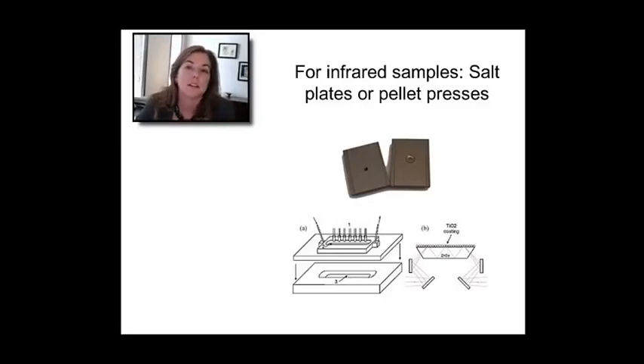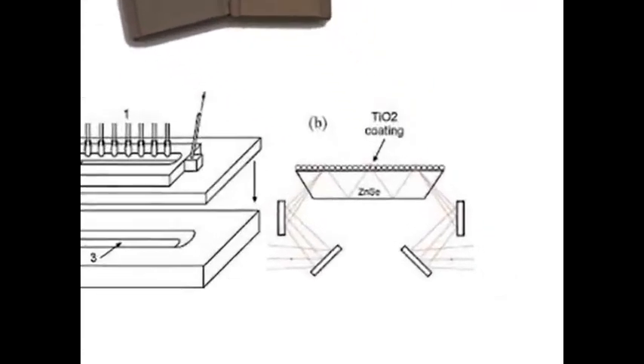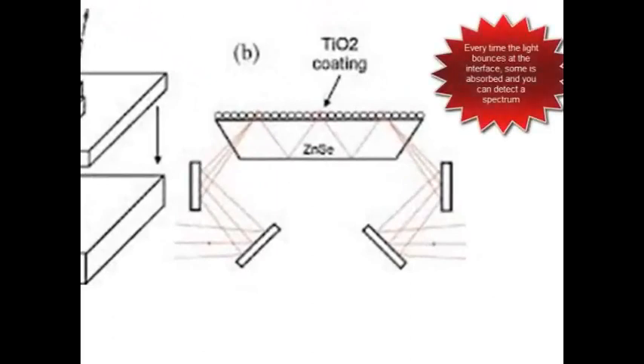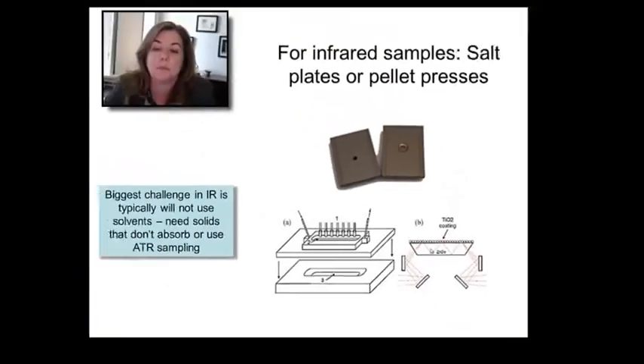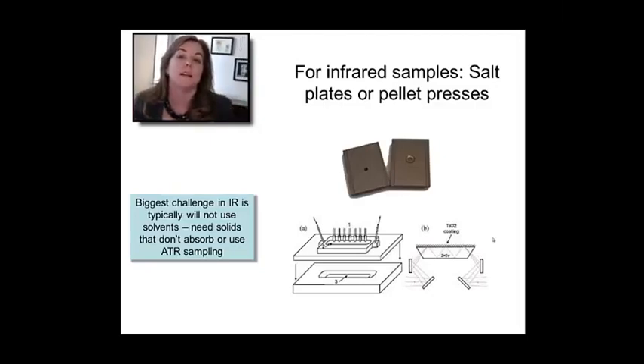One of the methodologies that is becoming a lot more common is actually attenuated total reflectance. So rather than putting the sample directly in the infrared light, you put it on top of something called an ATR plate, in which light's coming in but it's bouncing off the interfaces, as shown over here in this picture. And every time it bounces off the interface, it absorbs and interacts with some of the sample. Then it bounces down, so you can get a lot of passes in an ATR plate.